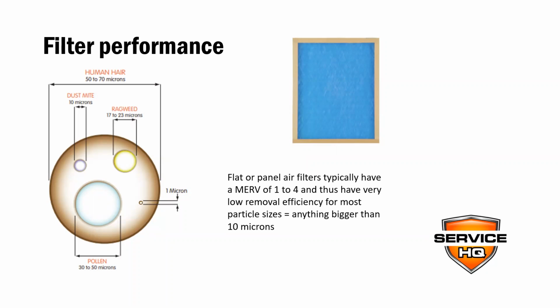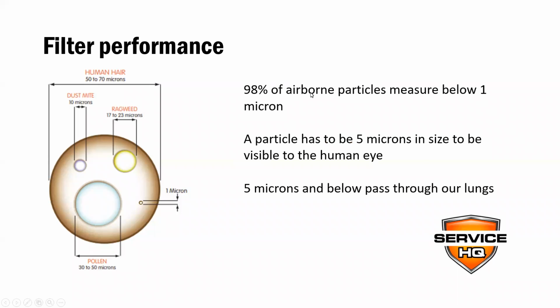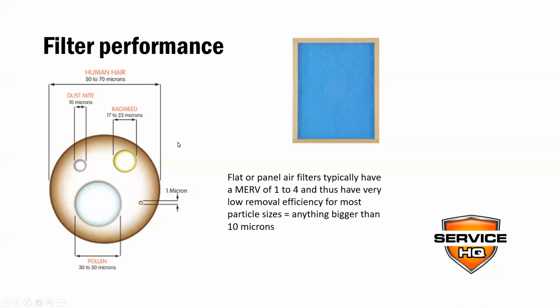So what that means is that they have a low removal efficiency for most particle sizes, which equals anything bigger than 10 microns. So it's got to be bigger than this one right here for this filter to catch it. And remember, we just talked about 98% of airborne particles measure below 1 micron. So this thing is just letting you breathe everything. This is the stuff you're breathing and it's passing through your lungs. Just not a good filter.